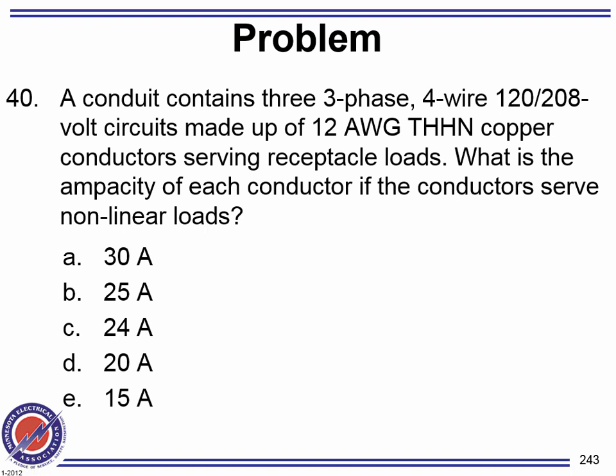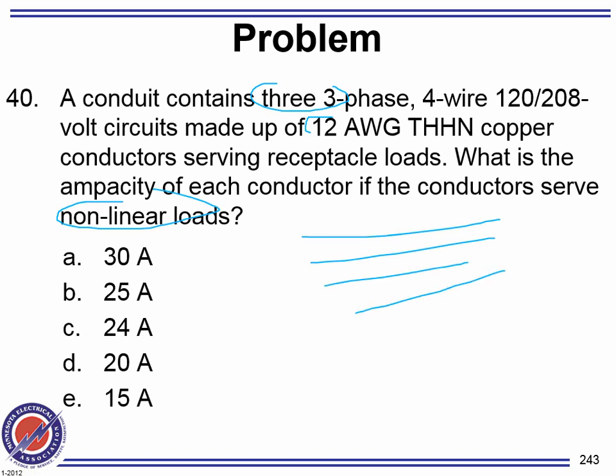A conduit containing three-phase, 4-wire, number 12, serving receptacle load. What is the ampacity of each conductor if the conductor serves nonlinear load? Okay, we have three phase. Let's count. 1, 2, 3, 4. Here's one circuit. And imagine 3 of these. How many conductors do we have?